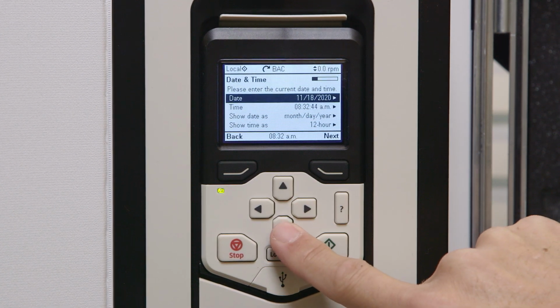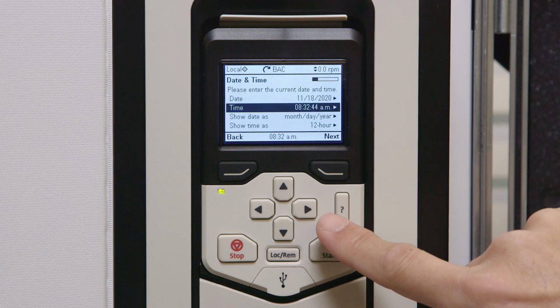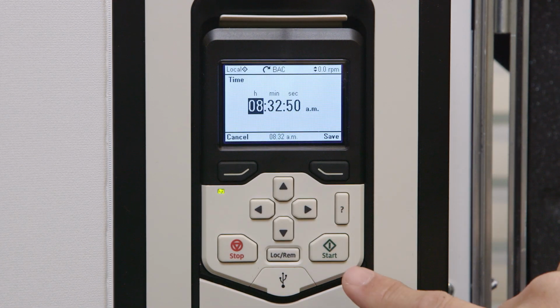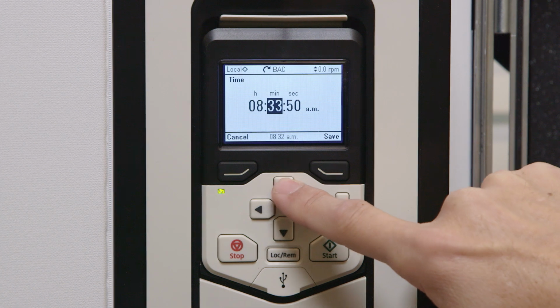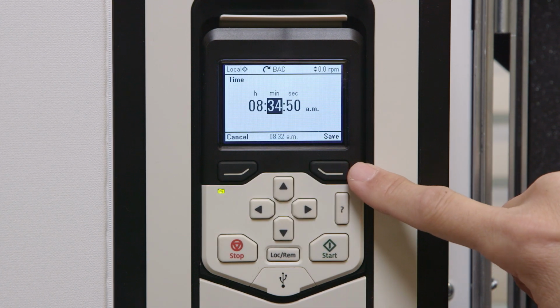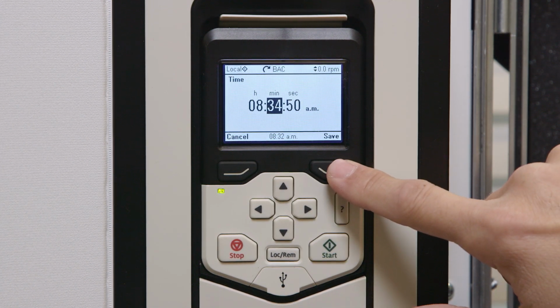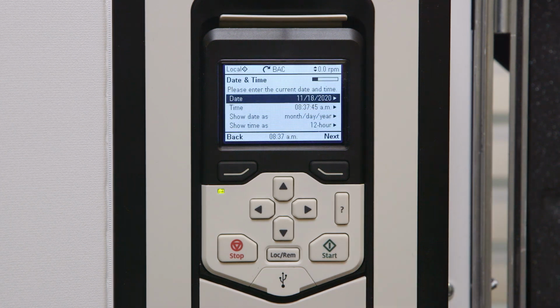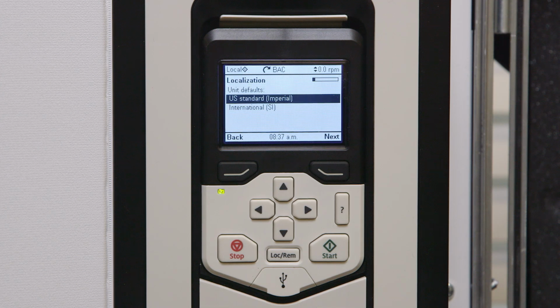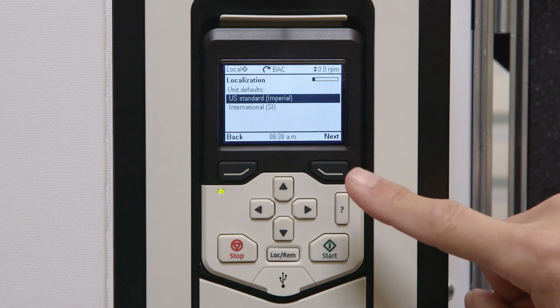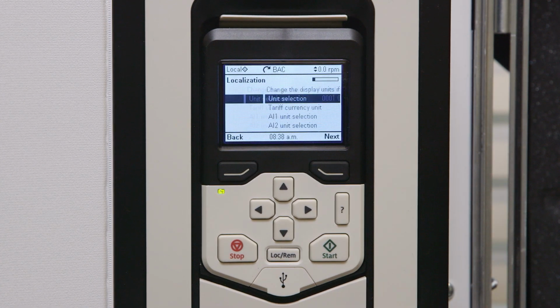Using the down arrow, scroll down to Time, then press the right arrow button on the keypad to adjust to the current time. Once the proper time is set, press the right Soft button to save the time. Press Next. Now that the date and time are properly set, the VFD will have us set the units of measurement on the display. You could choose either US Standard, Imperial, or International Metric units. Once you've highlighted the proper choice, press Next.